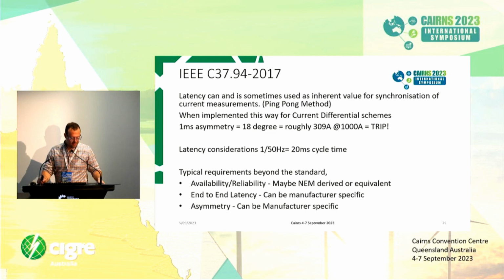Above and beyond what's in the standard, some of the additional requirements may include availability and reliability. It can be NEM derived or equivalent for your location. The end-to-end latency is not specified in the standard, so you need to be conscious of not only your cycle times, but also manufacturer specifications, and also asymmetry is not defined. So as we mentioned earlier, you need to consider how much asymmetry your schemes can tolerate.